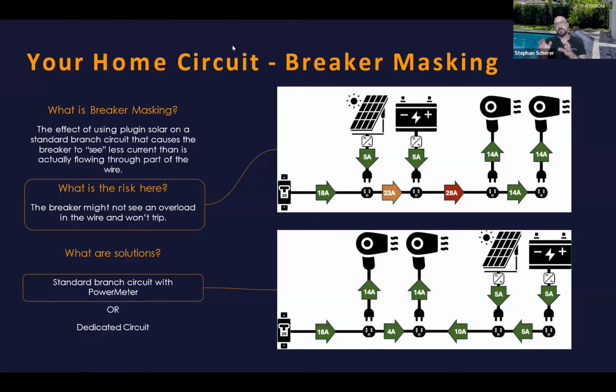So the NEC says, well, in that case, there's two solutions for you. One is written here or emphasized here. You have a power meter. That power meter allows you to measure exactly the usage on that circuit. Power meters are typically simple devices. They come with these clamps. We call them CT clamps, current transformer clamps. They measure the amperage through a wire. You click those around the wire.